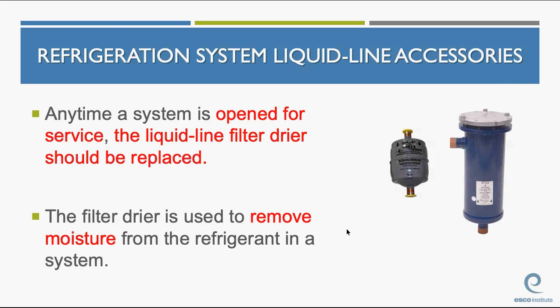Okay. Anytime a system is open for service, the liquid line filter dryer should be replaced. The filter dryer is used to remove moisture from the refrigerant in a system. Okay, this is another type of filter dryer here. This filter dryer over here has a changeable core in it. You don't replace the entire filter dryer.